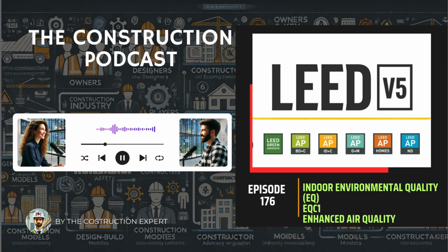Wow, okay. So option one, powerful in concept, just flush contaminants out with the sheer volume of fresh air, but it comes with a potentially very high price tag in ongoing energy consumption, and it demands extreme rigor in system sizing, sophisticated controls, especially for VAV, and meticulous commissioning to actually prove that 95% coverage in the breathing zone. That sums it up well. It's conceptually simple, but technically demanding to execute correctly and efficiently.